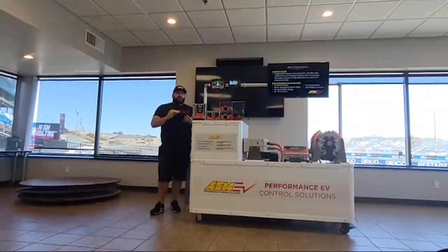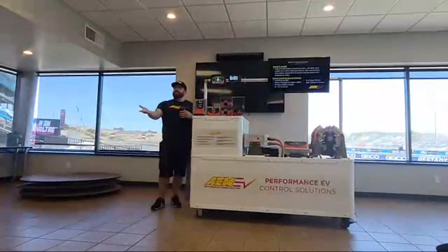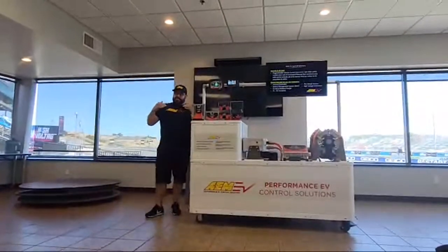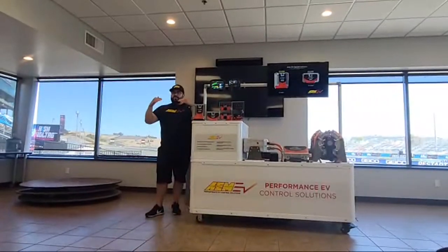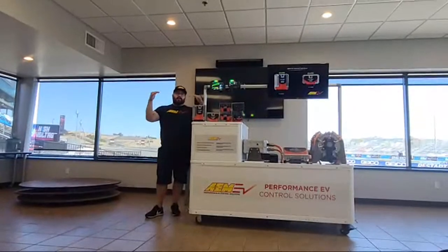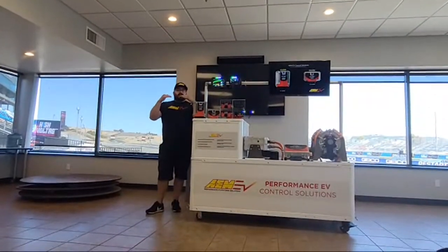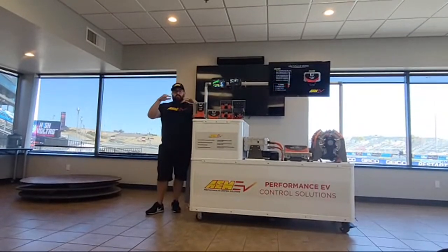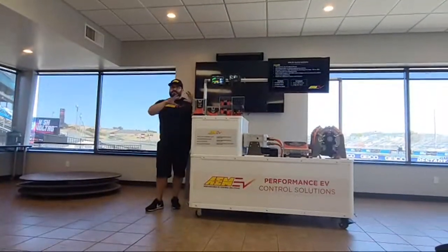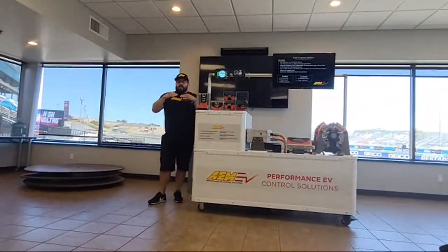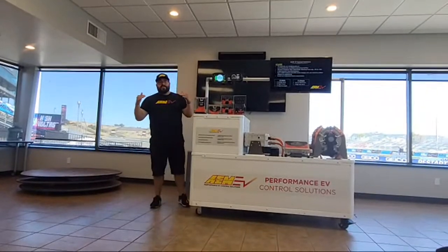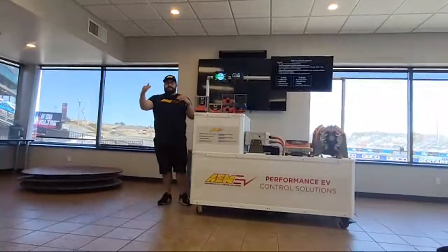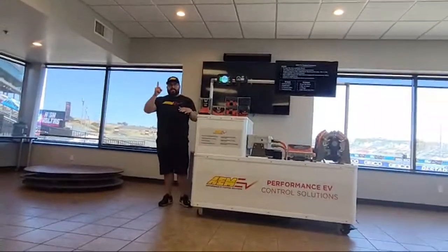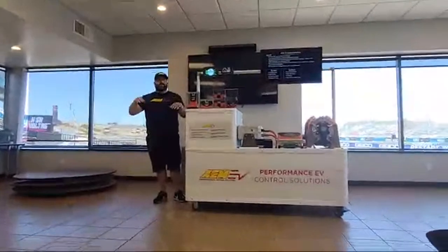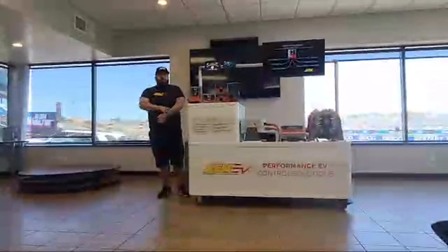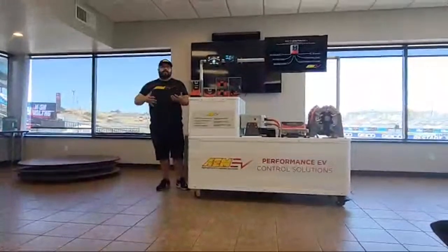So there's state of charge, pack voltage, individual cell voltage, and the concept of balancing. On the charge up, the voltages slowly increase toward that peak 4-volt-ish point, and since you can't overcharge any cell, whichever one winds up highest matters, because they won't all be the same. Over time the voltages drift, some a little high, some a little low. If your cutoff is 4.2 volts, the first cell that hits 4.2 stops the charge, even if the other 95 are behind, because continuing to push current into that cell would overcharge it, damage it, and make it unhappy.